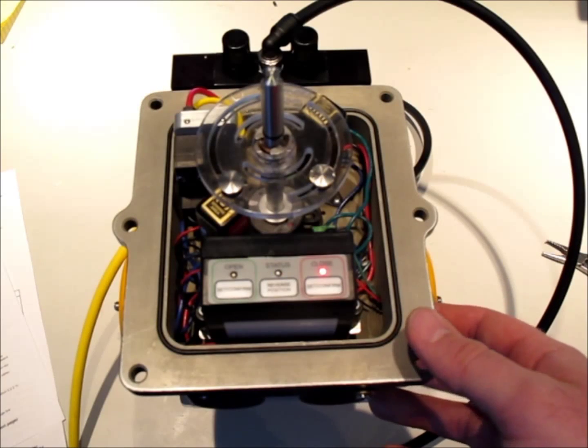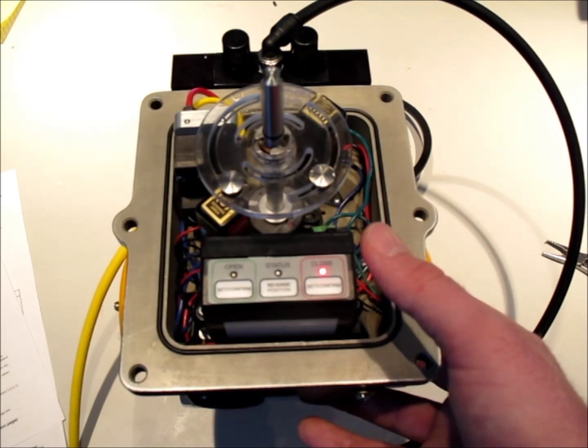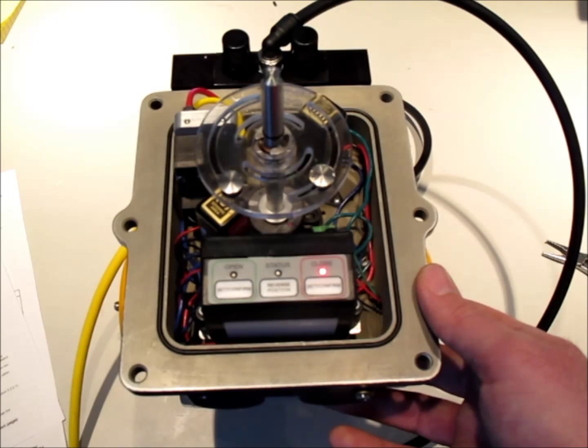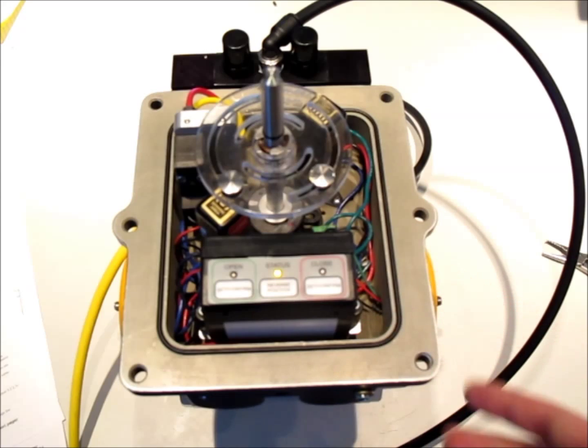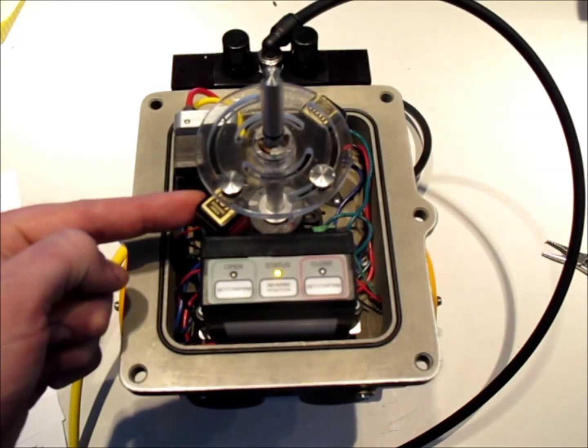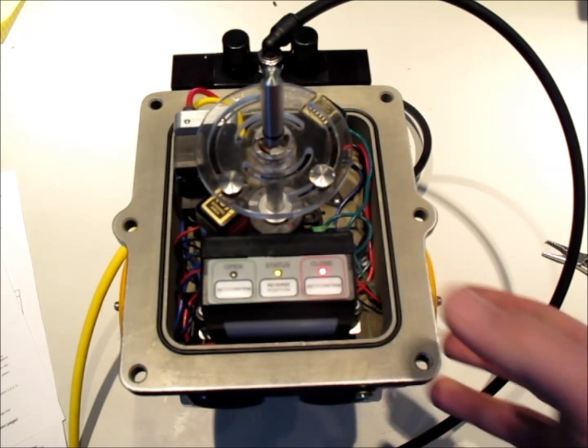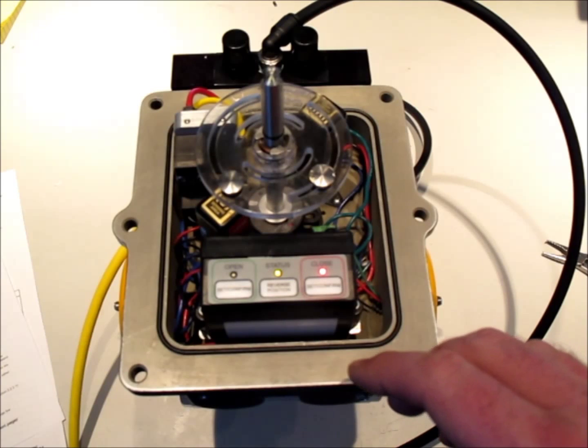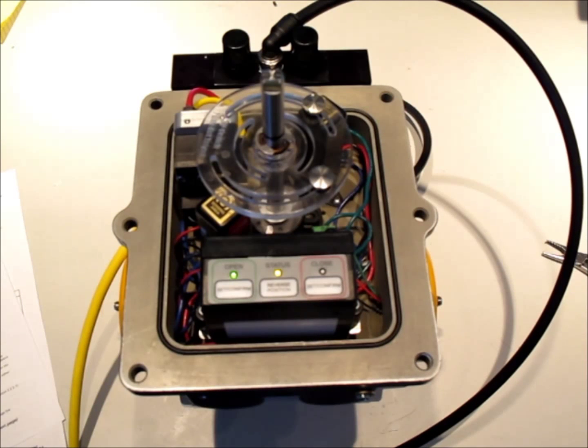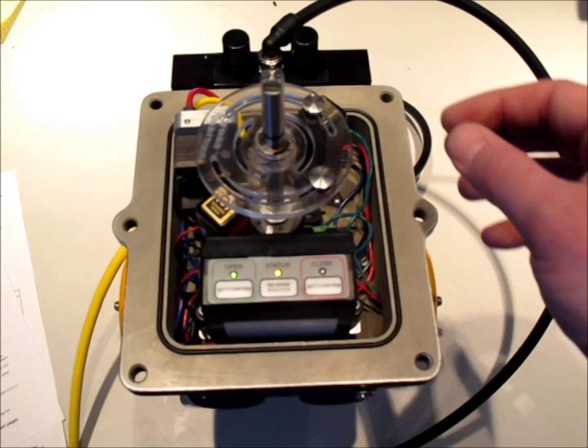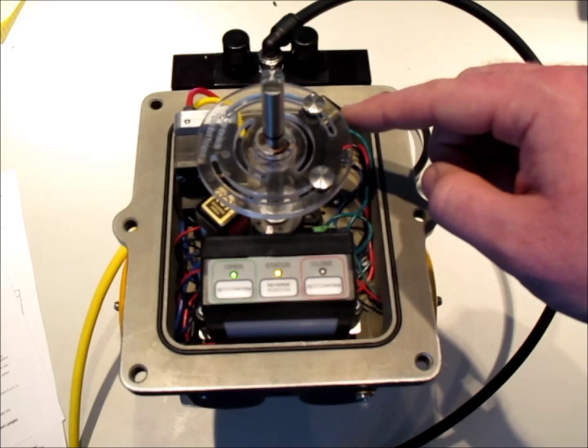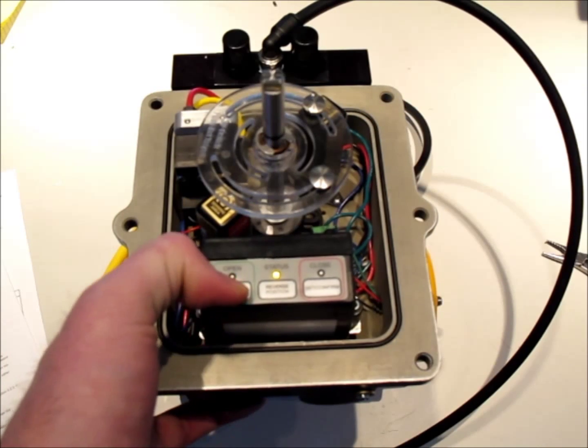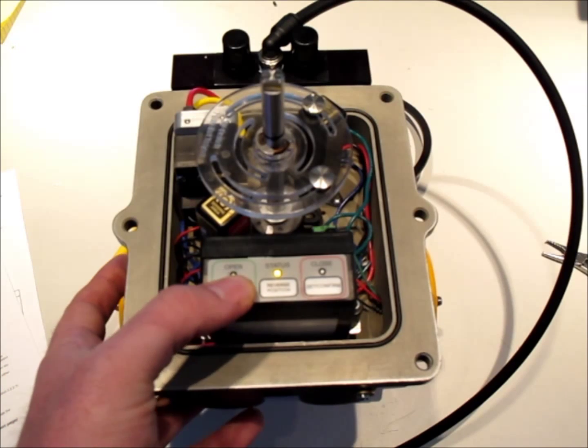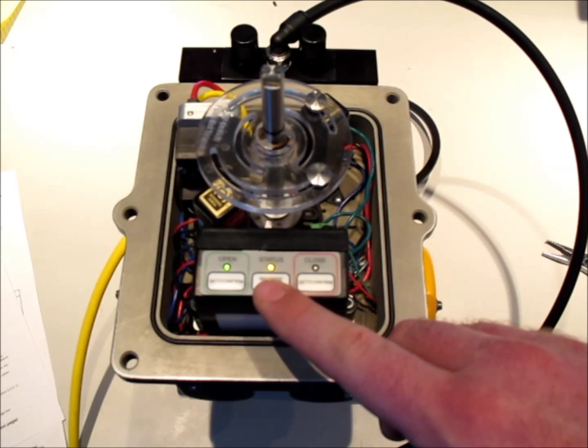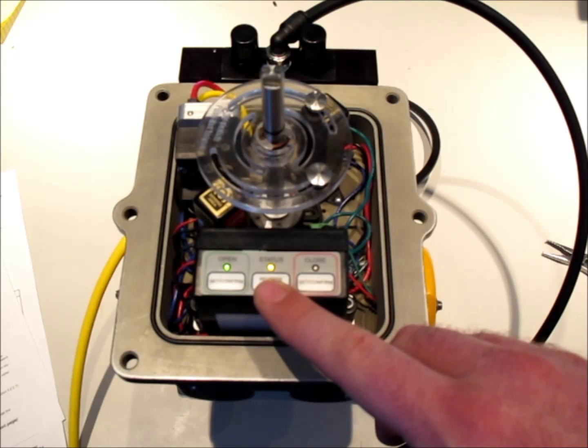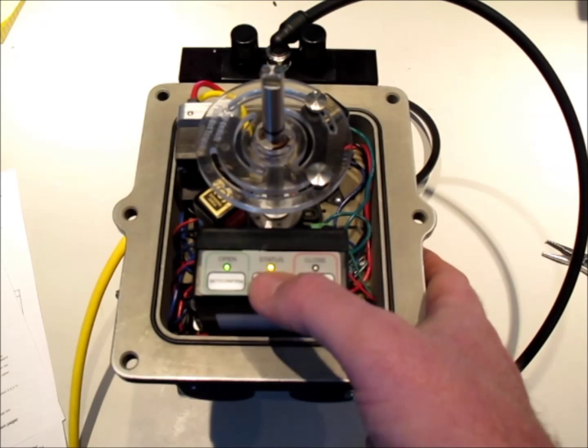To calibrate locally, i.e. not over DeltaV or with a handheld, move the actuator to the closed position and press the Set key. Once you've confirmed that the target magnet is in place and over top of the closed switch, confirm with the same button. Now if your transducer block is out of service, you can reverse the valve position. Once you've moved to the open side of the actuator, confirm that your open magnet is in over top of the open switch. Once again, hit Set to blinking, the magnet's in place, and now confirm. You'll notice that the status light has changed from a flash to now a solid light. This is letting us know that it is indeed calibrated.